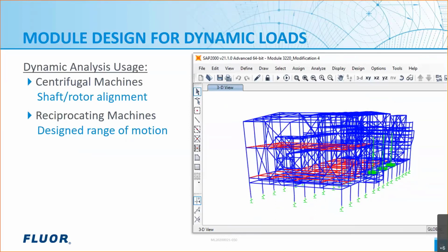The dynamics of vibratory machines is significant in that preconceived assumptions or a lack of experience with modularization can drive decisions on what equipment is or is not to be modularized. Thus, aspects of this subject are covered on the next several slides. Centrifugal machines are the most common type. The dynamic load originates from an imperfect shaft-rotor alignment, which slowly increases over time during operation. If the shaft and rotor are perfectly aligned, then there will be no vibration.